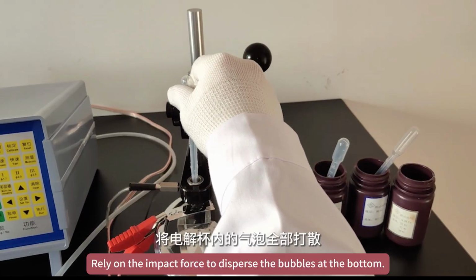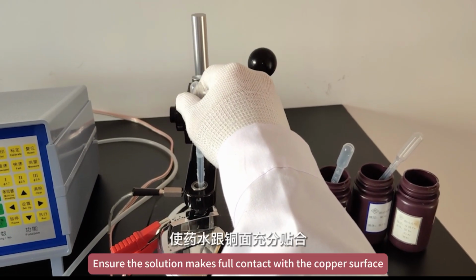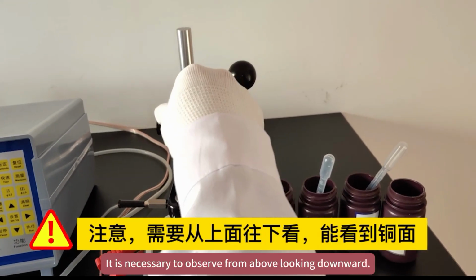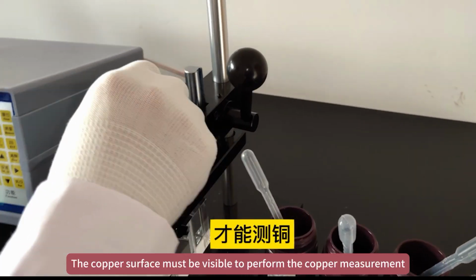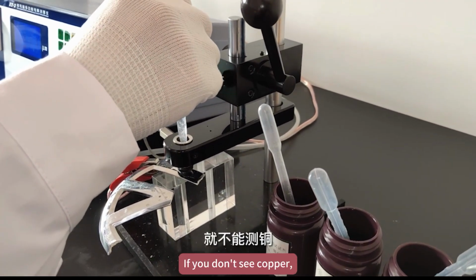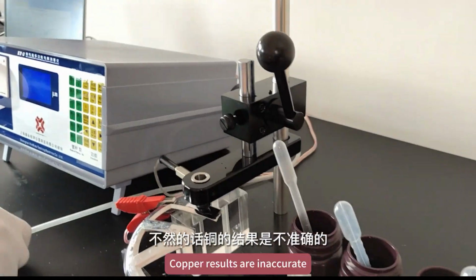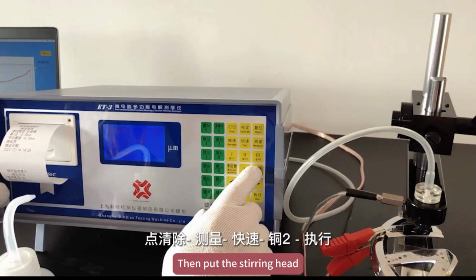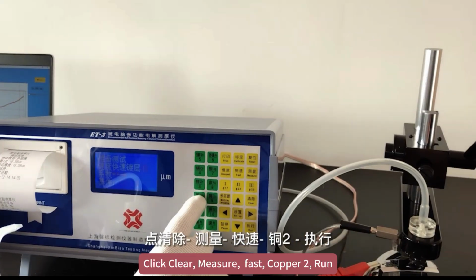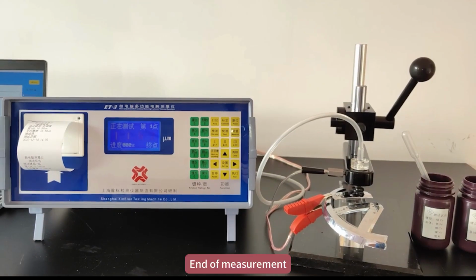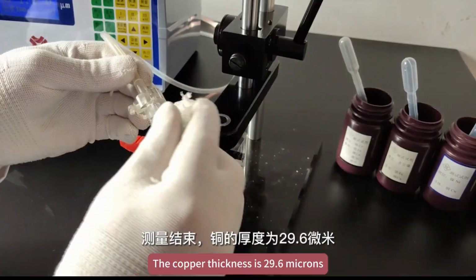Blow and suck repeatedly. Rely on the impact force to disperse the bubbles at the bottom. Ensure the solution makes full contact with the copper surface. Note, it is necessary to observe from above looking downward. The copper surface must be visible to perform the copper measurement. If you don't see copper, you can't measure copper. Otherwise, copper results are inaccurate. Then put in the stirring head. Click clear, measure, fast, copper 2, run. End of measurement. The copper thickness is 29.6 microns.